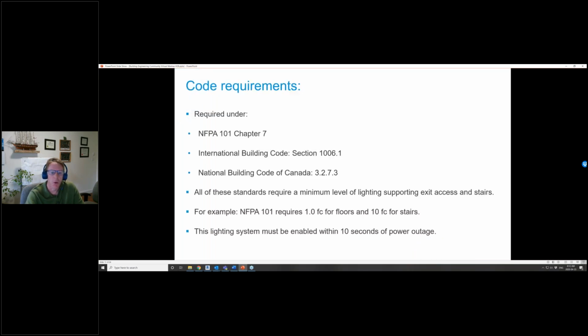So about the code requirements, some examples: NFPA 101 Chapter 7, the IBC 1006, and here in Canada, National Building Code 3273. All these standards require a minimum level of lighting. NFPA, for example, requires 1-foot candle on floors, 10-foot candles for stairs. Canada's similar. I'm not sure about IBC. NFPA requires the lighting system to be enabled within 10 seconds of the power outage.